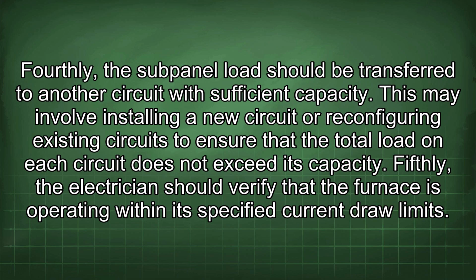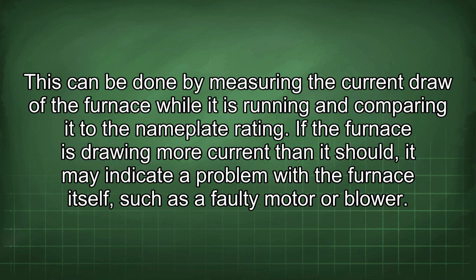Fifthly, the electrician should verify that the furnace is operating within its specified current draw limits. This can be done by measuring the current draw of the furnace while it is running and comparing it to the nameplate rating. If the furnace is drawing more current than it should, it may indicate a problem with the furnace itself, such as a faulty motor or blower.